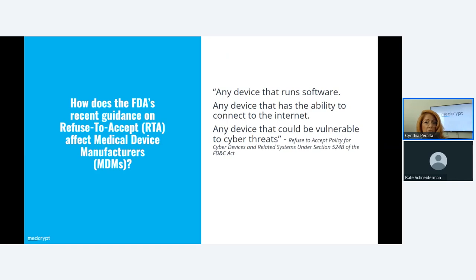So submissions for new medical devices will need to include things such as the description of a plan for identifying and addressing vulnerabilities and exploits in a reasonable time, details on the processes and procedures for releasing post-market updates and patches that address security issues, regular updates, as well as providing out of band. So what that means is anything that's sent outside of the release cycle, over the air patches in the case of critical vulnerabilities. Let's see how this translates to encryption, key management, and PKI for medical devices.